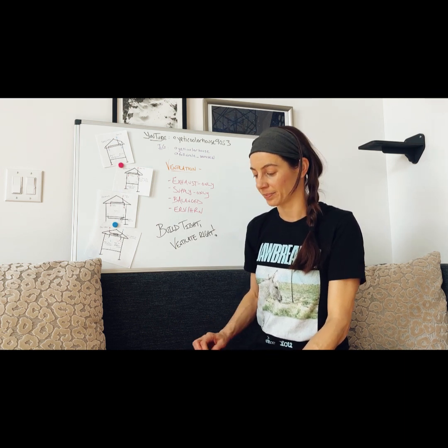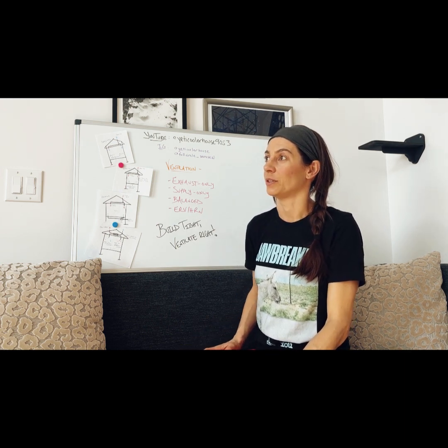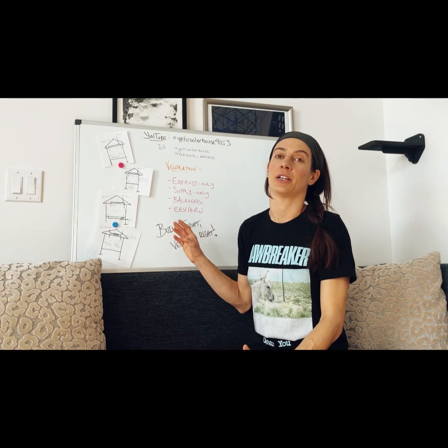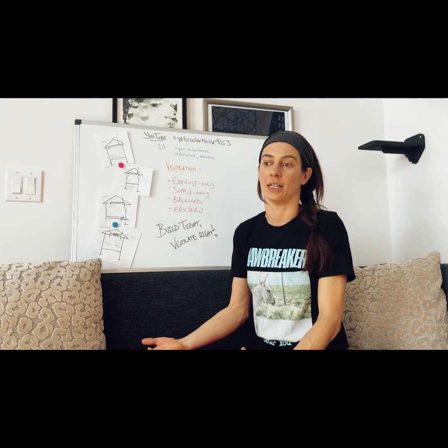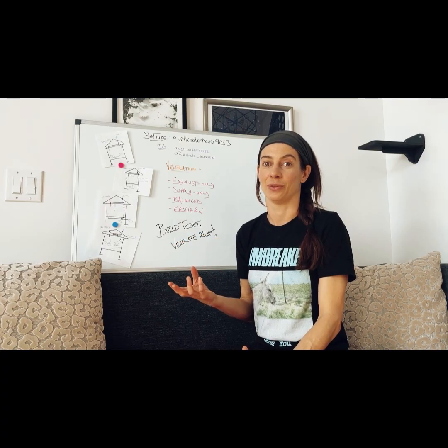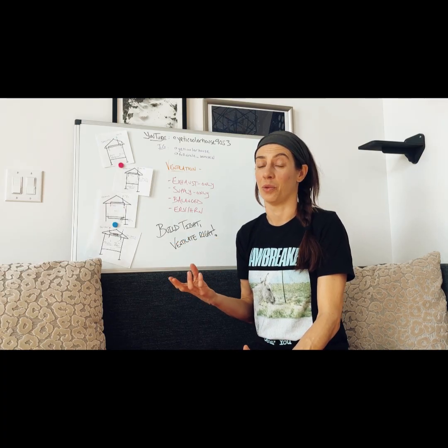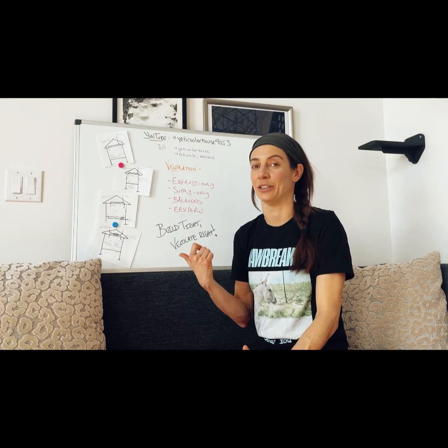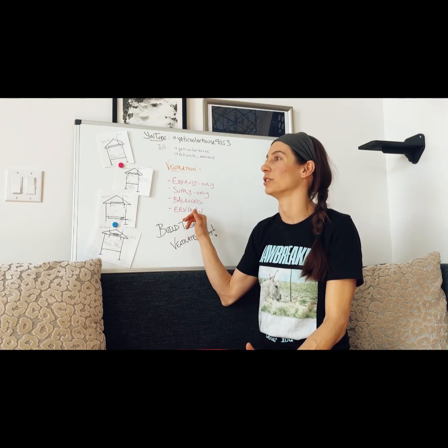So that's pretty neat. Typically the ERV is recommended in a drier climate because you want to maintain that moisture in the house, whereas in more humid climates you're trying to dehumidify, right? So you would go with the HRV.